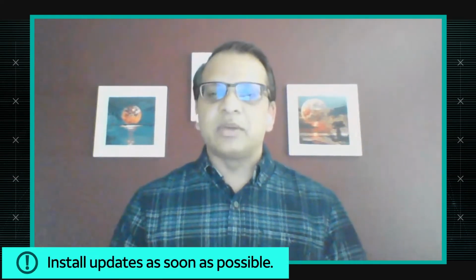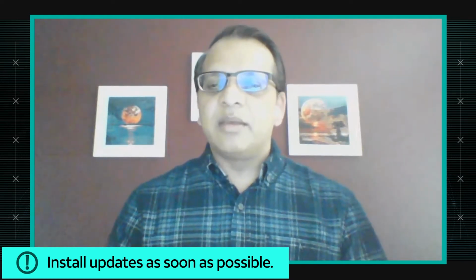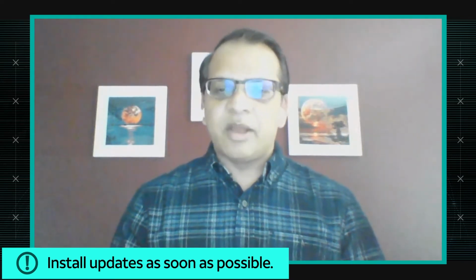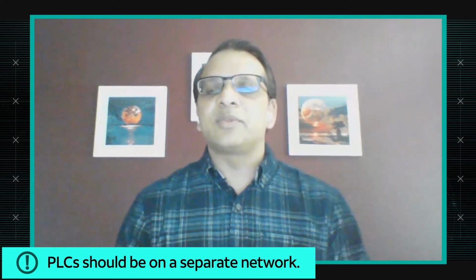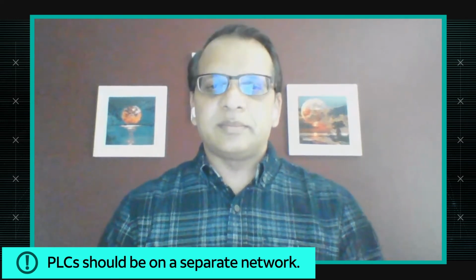So what is the protection against this vulnerability? Yeah, luckily, I think last Friday, Siemens came up with a firmware update which will fix this avenue. The protection would be, first of all, whenever possible, try to get the latest update. Meanwhile, if it takes some time to get the update, it's always a good idea to segregate these PLCs from the regular network and keep them inside some sort of secluded network.